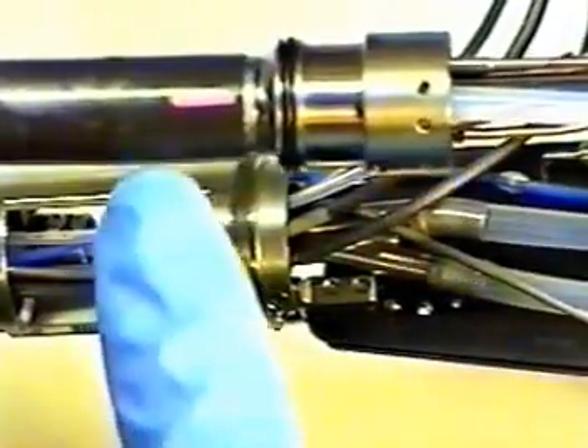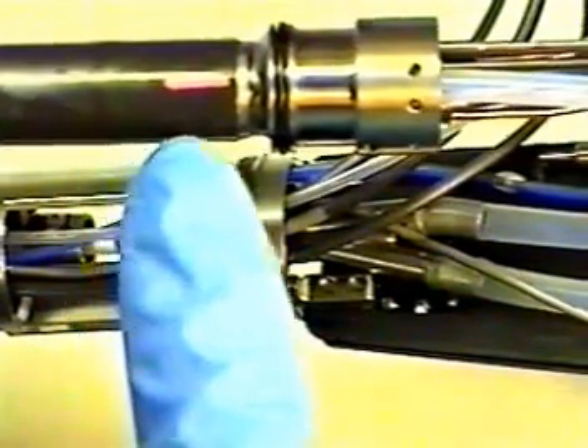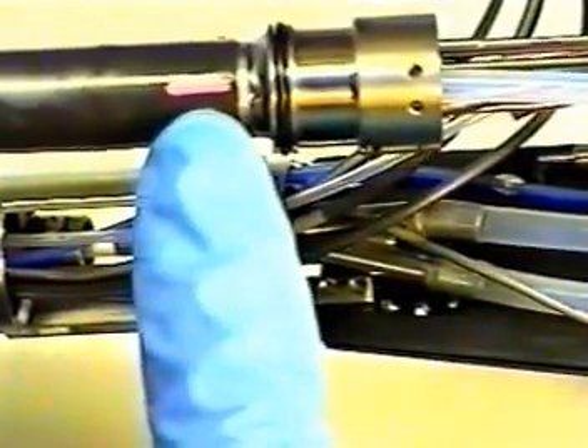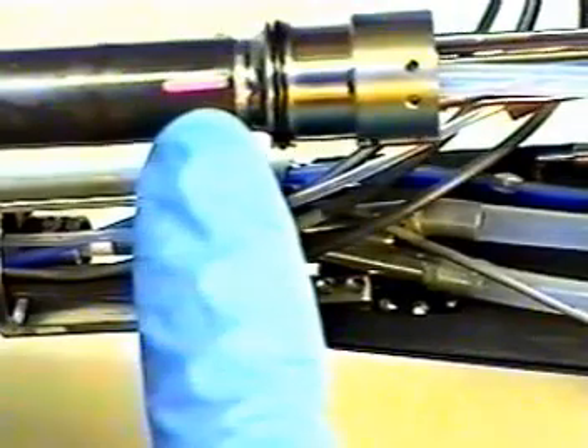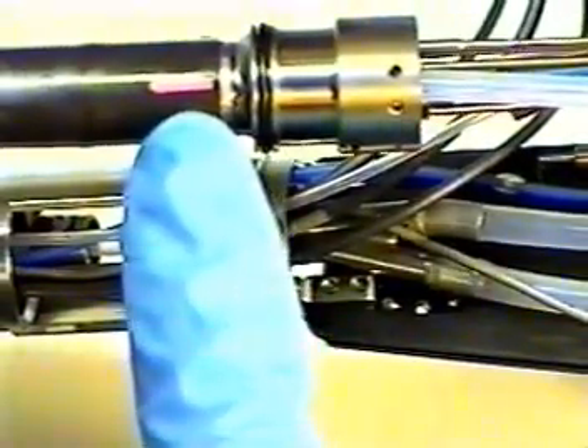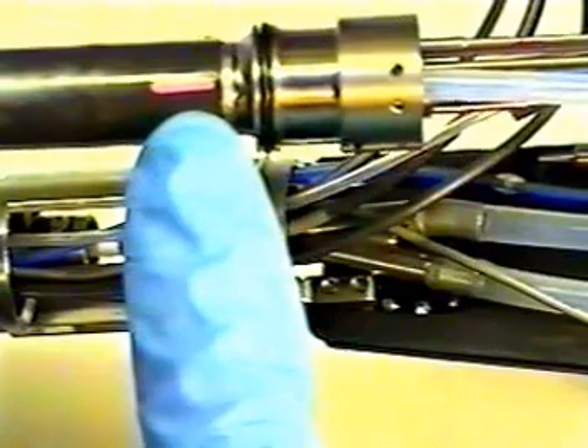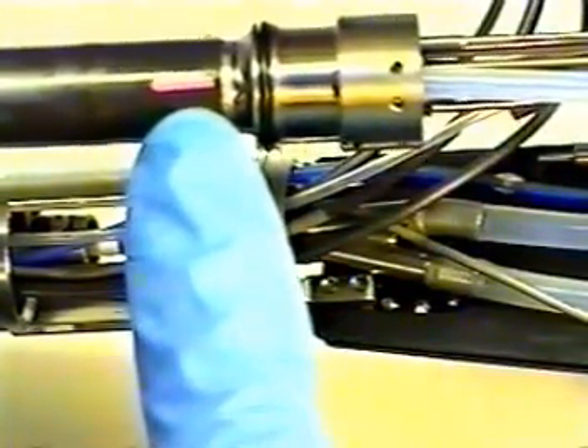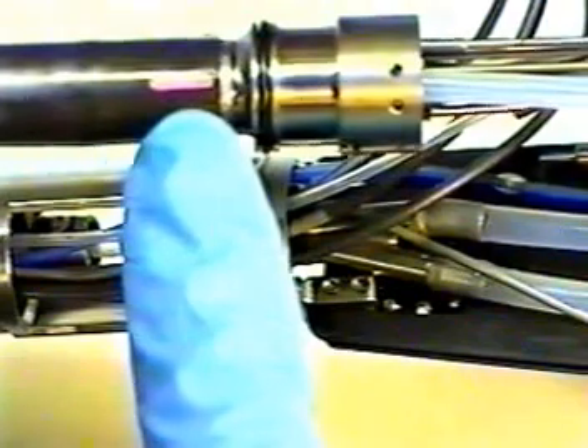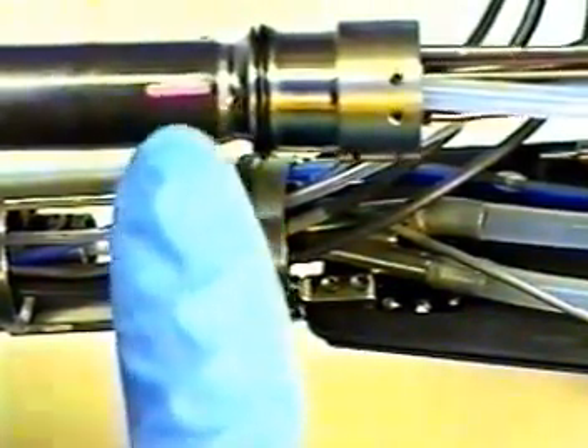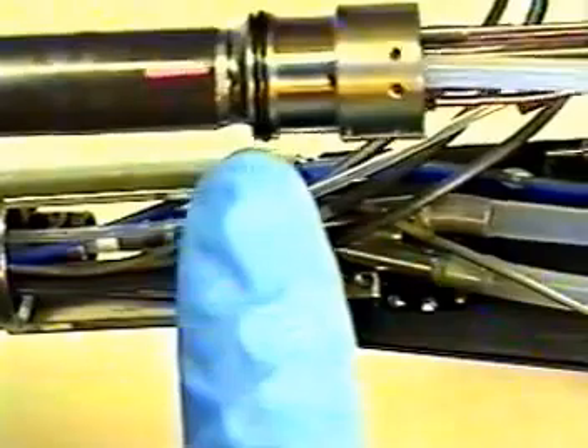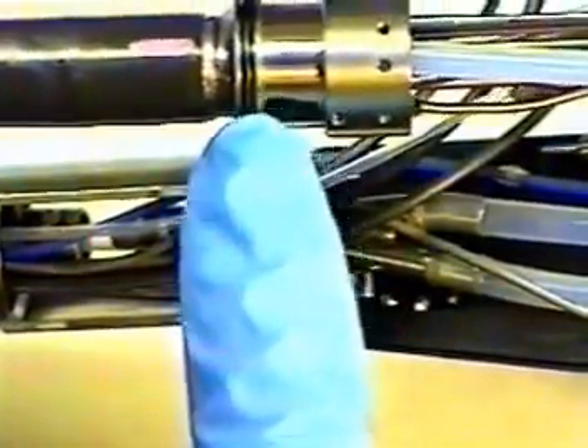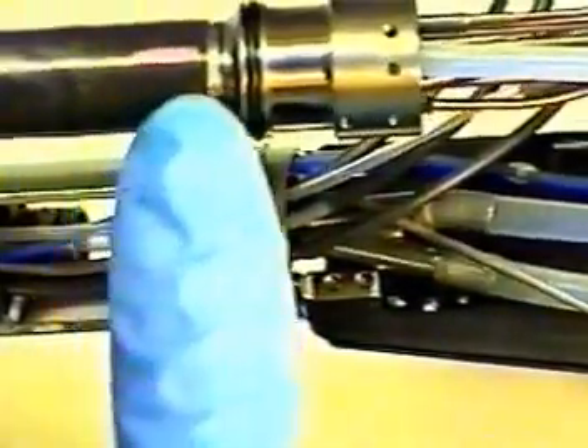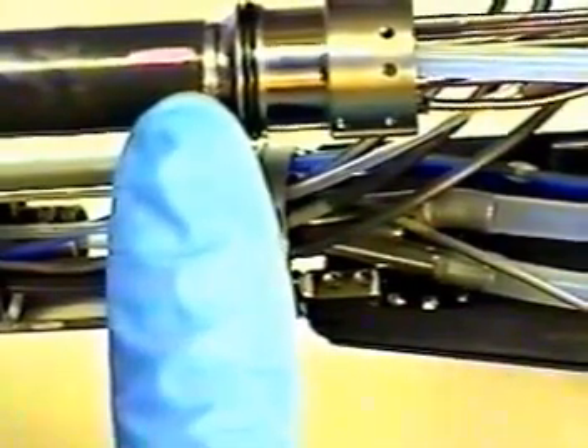When pulling through the new refurbished ISA assembly at the factory, it is usually orientated up, which will go on top of the body control section, so the angulation will be correct and the image of the CCD will not be upside down. You will match the marking from the factory or marking that you previously had on the ISA assembly to the top of the body control section, so the up, down, left, right cables are correct and the image is right side up.